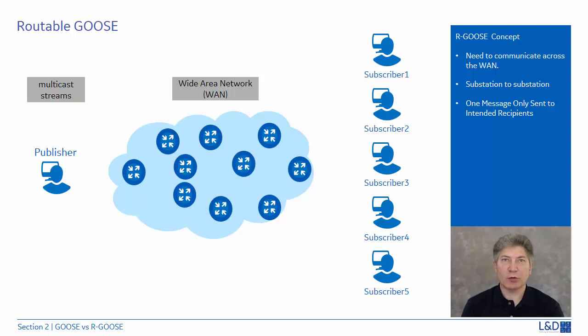The routable GOOSE concept was created for substation to substation communications across a wide area network. Previously, we spoke about the standard GOOSE where we were broadcasting to everyone. In the routable GOOSE, the message will use a multicast approach on a wide area network and only send a message to intended recipients. Based on this, a security issue was raised. The routable GOOSE will need to implement a security component to authorize and authenticate those recipients. We'll talk more about that in the next section.